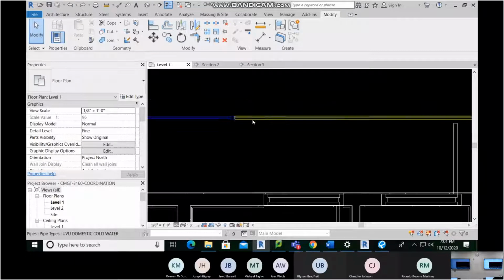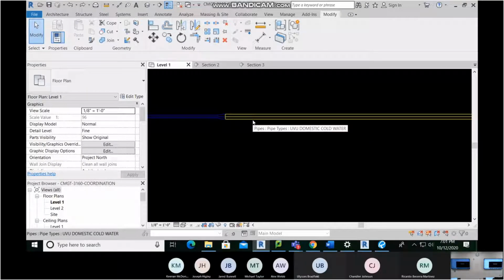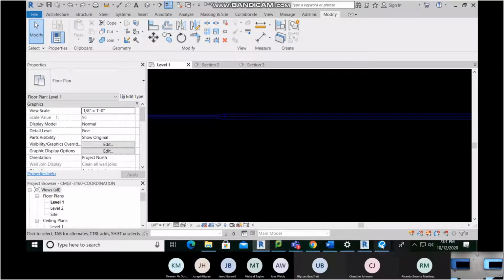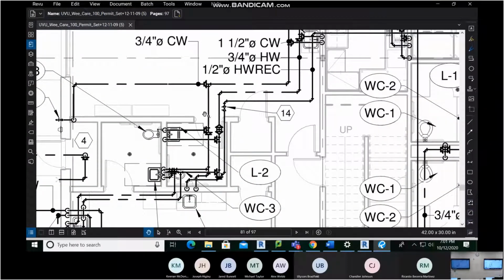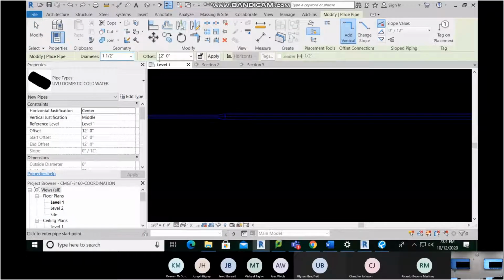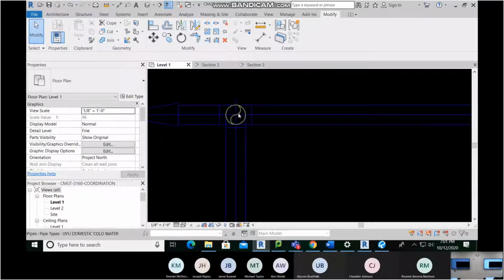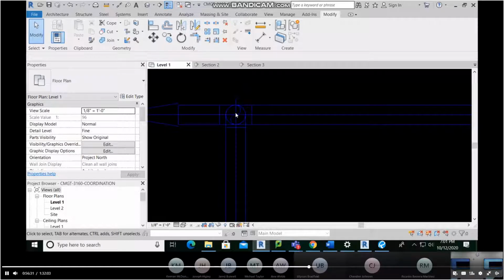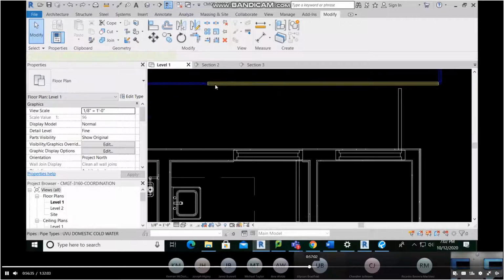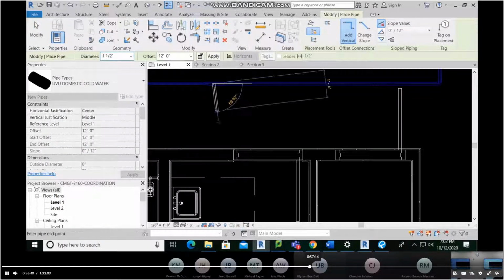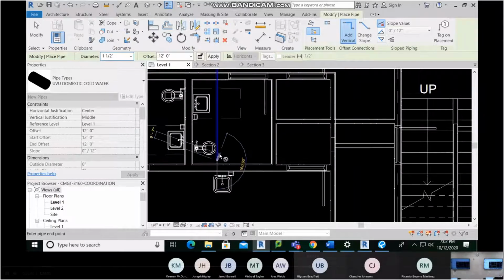When you create similar, you can also change the elevation. So if I wanted to create an offset here for whatever reason, and technically, looking at the plans, you don't have to, because you would consider this still at the same elevation, because they never cross over. It's these pipes and these lines that cross over. But if you wanted to create an offset right away, you can by doing create similar, so CS, changing your elevation to 12'6", hitting enter, and then drawing in your pipe, and you'll notice it created an offset for me. The offset is indicated by that circle. If you're looking down the pipe, that's where you get your offset from. So you can do it that way as well. But for this instance, we're just creating similar. We're keeping it at 12 foot, keeping it at 1.5 inches, and just drawing straight down.